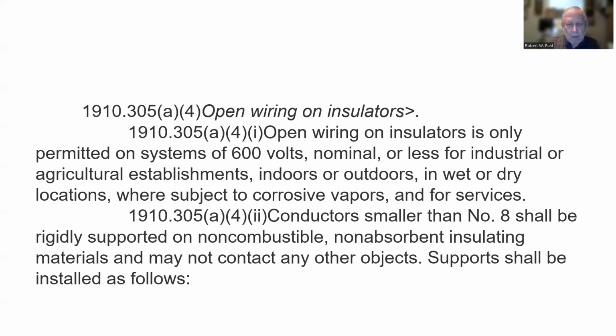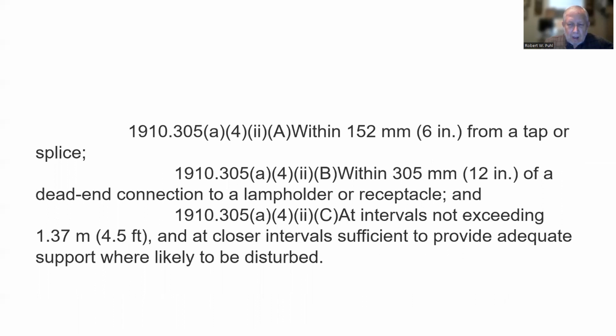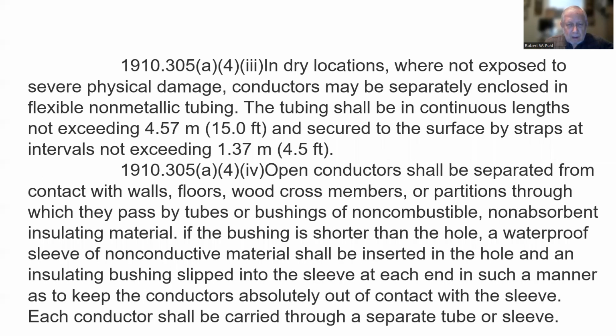Open wiring on insulators. Open wiring on insulators is only permitted on systems of 600 volts nominal or less for industrial or agricultural establishments, indoors or outdoors, in wet or dry locations, or where subject to corrosive vapors, and for services. Conductors smaller than number 8 shall be rigidly supported on non-combustible, non-absorbent insulating materials and may not contact any other objects. Support shall be installed as follows. And I'm not going to get into that too much. In dry locations where not exposed to severe physical damage, conductors may be separately enclosed in flexible nonmetallic tubing. And there's the length and straps that support it, 4.5 feet.